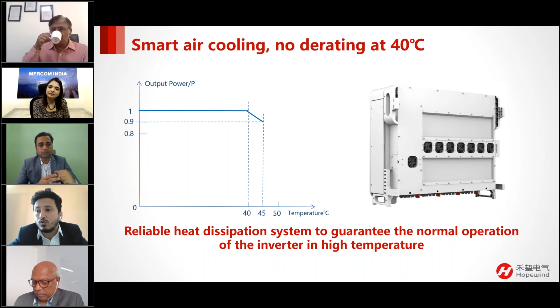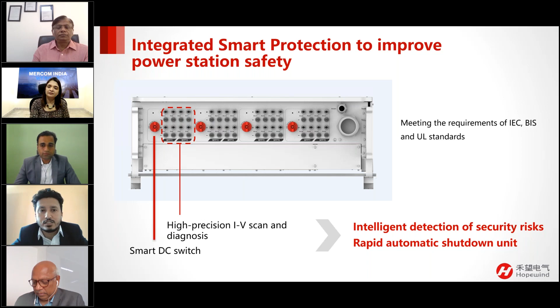If we talk about smart protection, our 385 kilowatt inverter comes with a smart DC switch, which enhances the safety and reliability of the solar power plant. This smart switch protection helps to prevent electrical faults on the DC side. It comes with features like over voltage and under voltage protection, over current protection, ground fault monitoring, and compliance with grid safety standards and regulations such as IEC 62109.